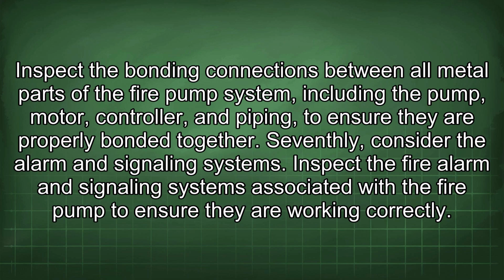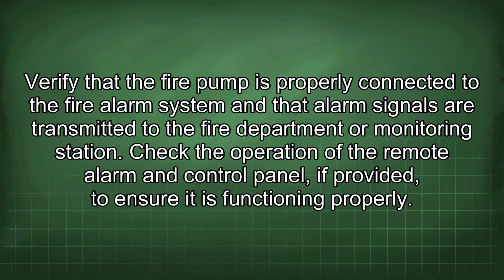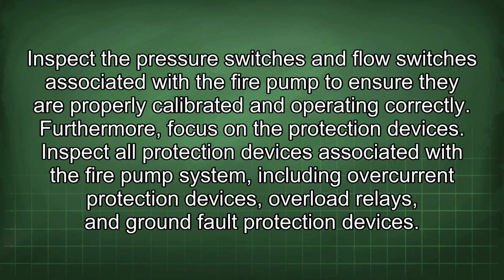Seventhly, consider the alarm and signaling systems. Inspect the fire alarm and signaling systems associated with the fire pump to ensure they are working correctly. Verify that the fire pump is properly connected to the fire alarm system and that alarm signals are transmitted to the fire department or monitoring station. Check the operation of the remote alarm and control panel, if provided, to ensure it is functioning properly. Inspect the pressure switches and flow switches associated with the fire pump to ensure they are properly calibrated and operating correctly.